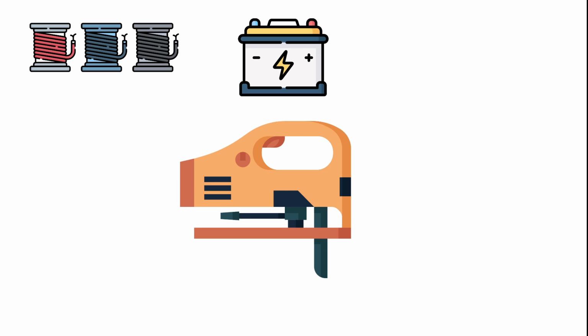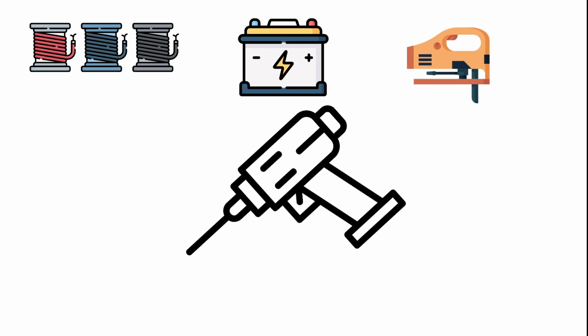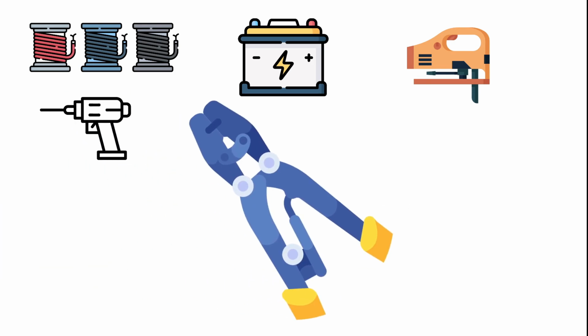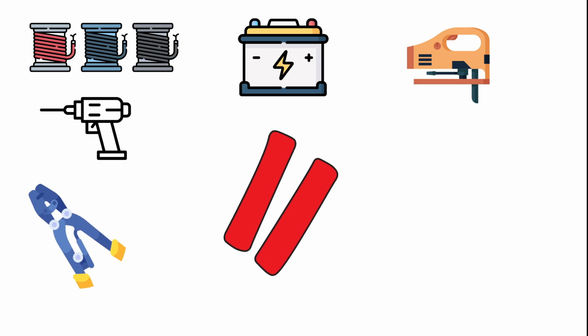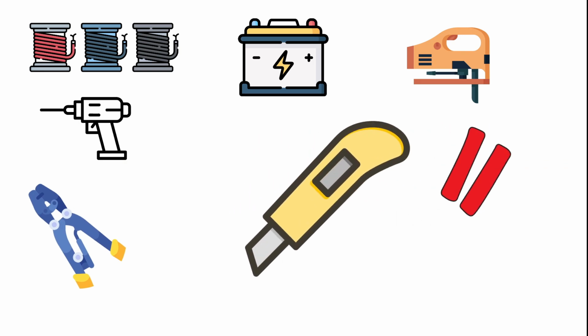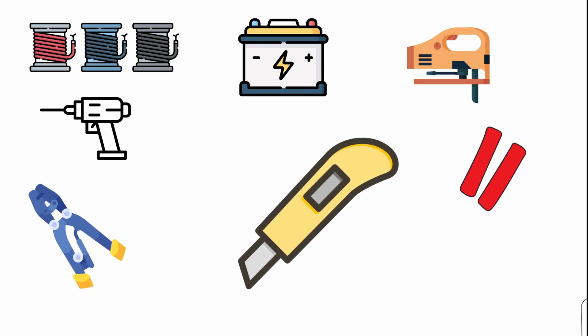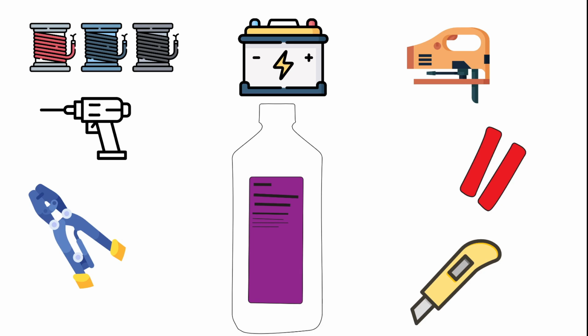Something to cut a hole in the wall where you will be installing your monitor panel, such as a jigsaw. A screwdriver or power drill to mount the faceplate. An 1/8-inch drill bit for a pilot hole for the faceplate screws. Crimpers for the butt connectors. Additional butt connectors or wire nuts may be needed. A razor blade to trim the foil. Isopropyl alcohol to clean the tank for tape application.